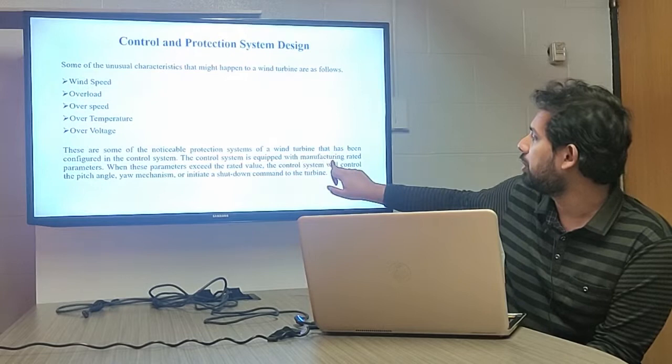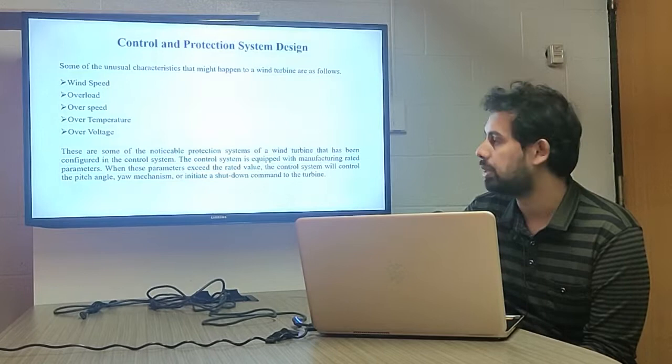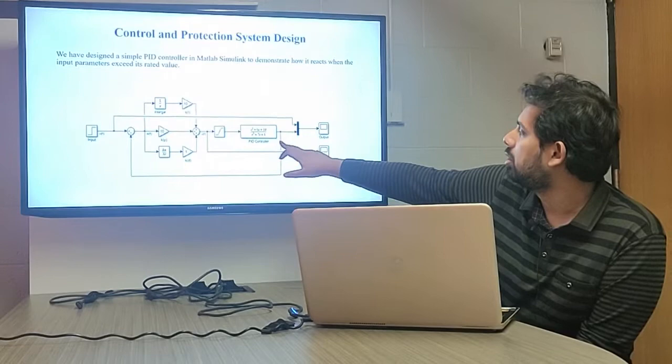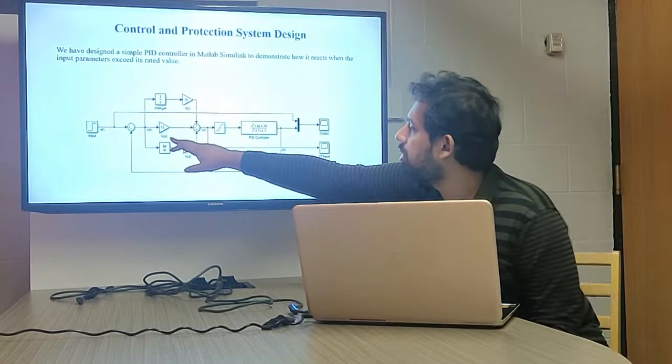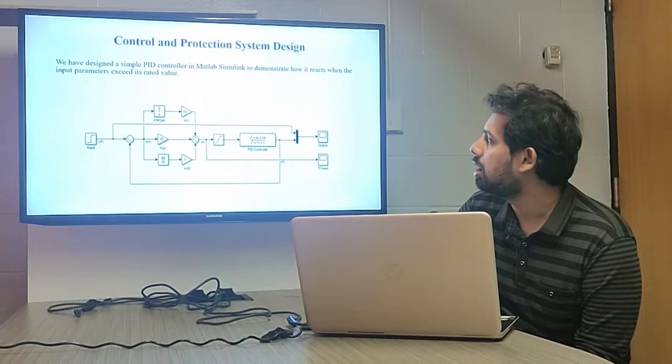The control system is equipped with manufacturer-rated parameters. When a rated parameter is exceeded, the control system will control the pitch angle, yaw mechanism, or even initiate a total shutdown of the wind turbine. The summation block in the PID controller continuously monitors the output variables; when output variables exceed the rated value, it signals the proportional, integral, and derivative blocks to keep the output variables within the rated value.